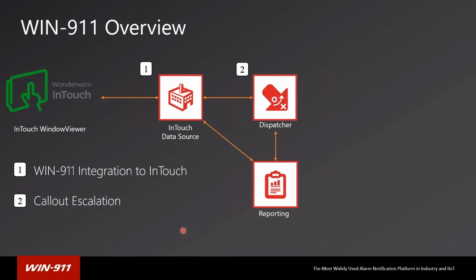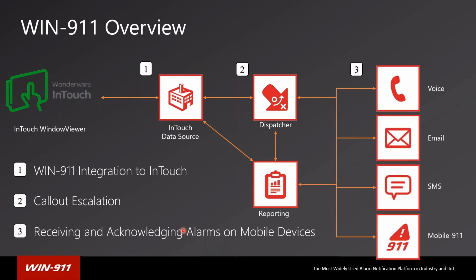And you can think of that like the middleman. If you're again looking at the workspace and you go to our notifications module, you'll see our strategies and tactics. And that's really what makes up the dispatcher module. When the alarm is triggered, it triggers a strategy, and then that strategy will trigger a tactic, which is your call out list. And from there, it hits the notifiers. Depending on which notifiers you select, you could have them all set up if you'd like.